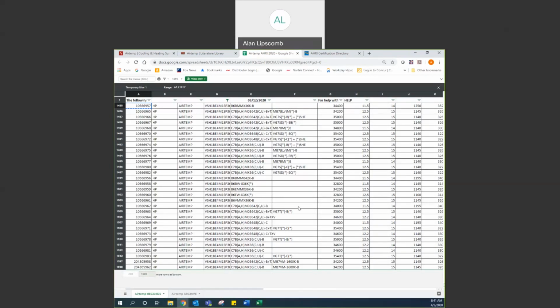Sometimes you see, like, we don't have a furnace here. So let's say you have a customer that comes in and says, hey, I need a condensing unit and a coil because all I'm going to do is replace those two items because my furnace is still in good shape. So what you would look for is a coil matchup minus a furnace. And as long as the existing furnace can drive the CFM that is required for the matchup and cooling, it would be a good fit, and you could sell them that system, and they could use that existing furnace.